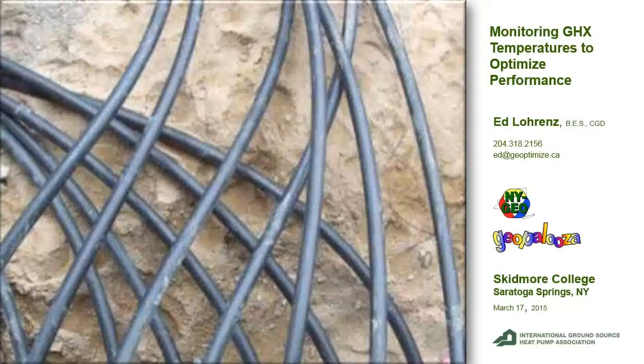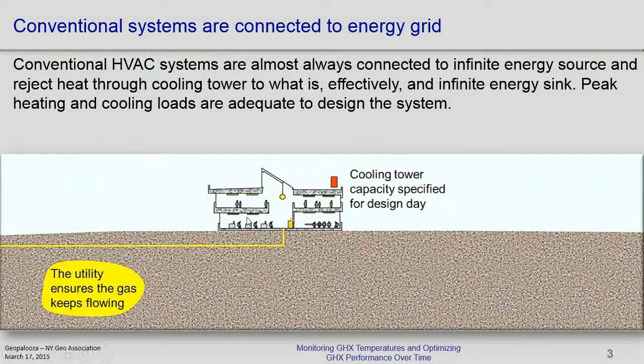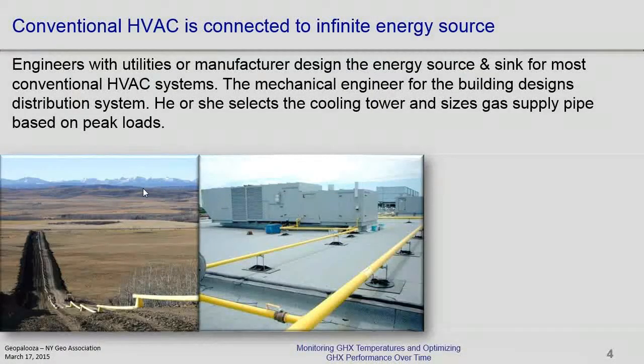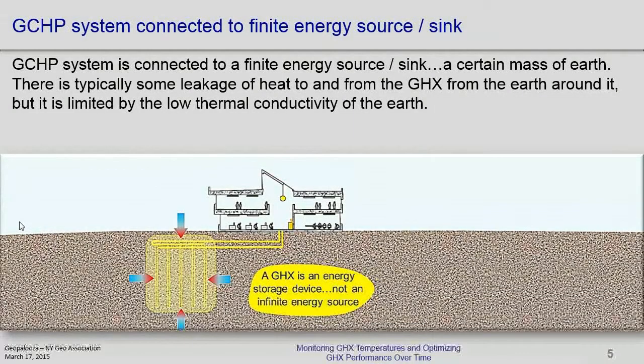Anyways, monitoring systems. I think the last part of the flow chart that I showed you was the operation of the system. And that, I've come to realize, is probably a fairly big deal. Again, with the conventional system, you're working with basically an infinite energy source. As long as there's gas lines out there, somebody, an engineer down at the far end of the line, is making sure that you've got enough gas coming down the pipeline to heat the whole city of Albany or the whole city of New York or whatever. You don't have to worry about it as a designer. But with a ground source, you're designing that energy source.